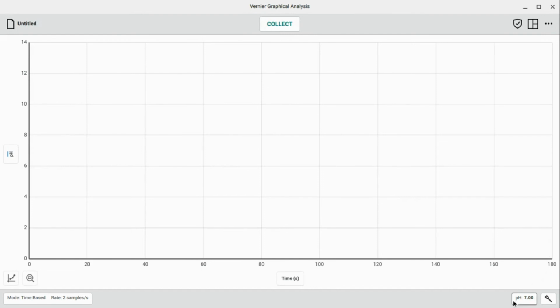And there you go. Again, it's in a buffer system with a pH of 7.00. And so we have it properly calibrated because it says 7.00 when it is, in fact, in a buffer that we know the pH of. So there you go. That's how to calibrate the Vernier pH electrode.